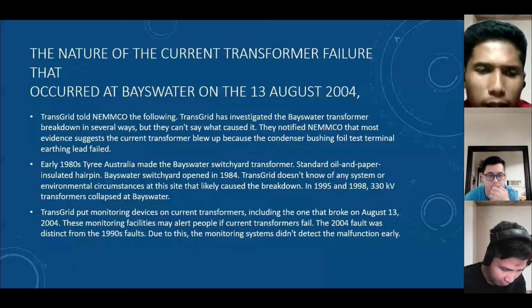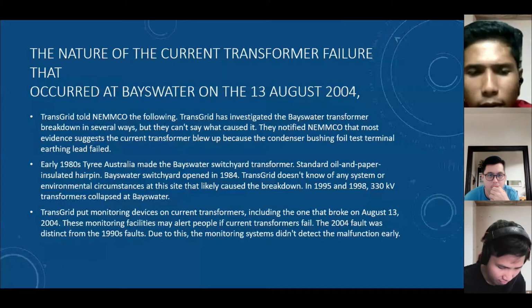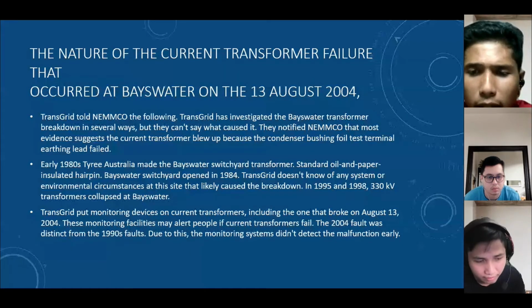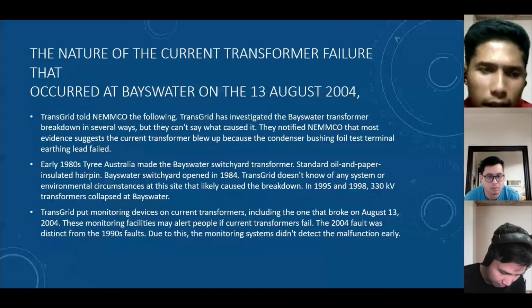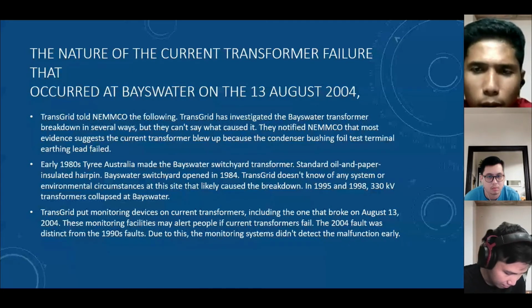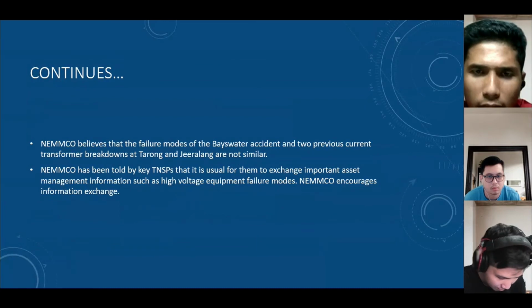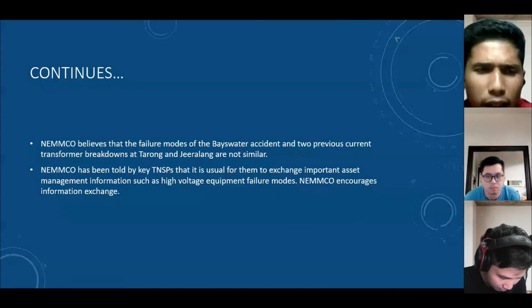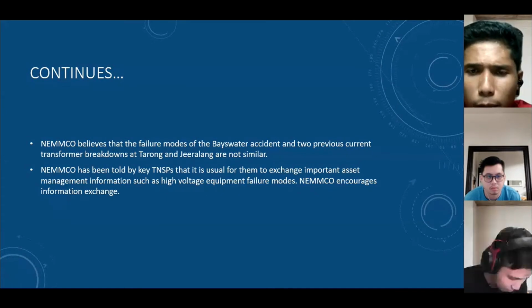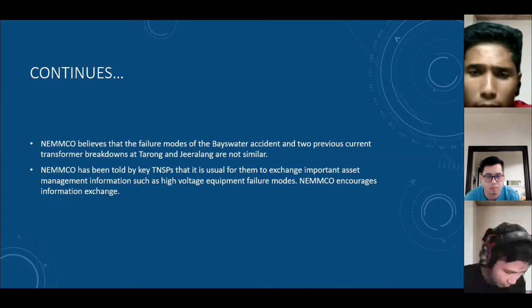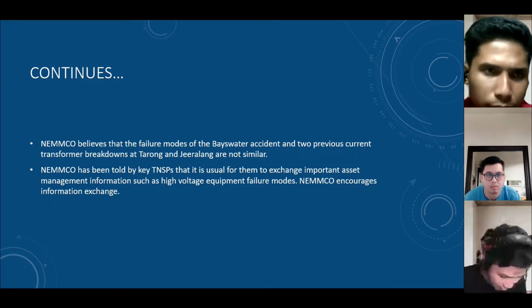The fault was distinct from the 1990 fault. Due to this, the monitoring system did not detect the malfunction early. NEMMCO believes that the failure mode of the Bayswater accident and two previous current transformer failures at Tarong and Jeeralang are not similar. NEMMCO was told by the TNSPs that it is unusual for them to exchange important asset management information such as important equipment. Alright, next we'll continue with my team member.